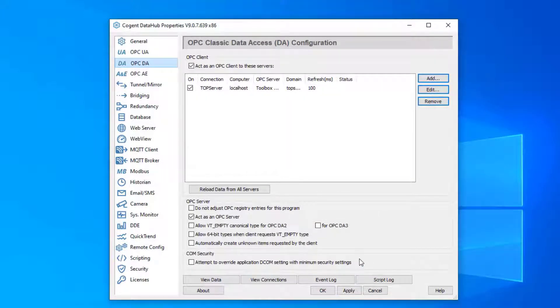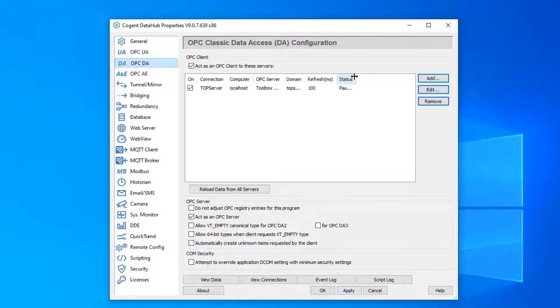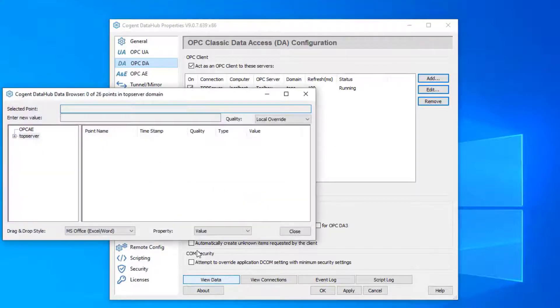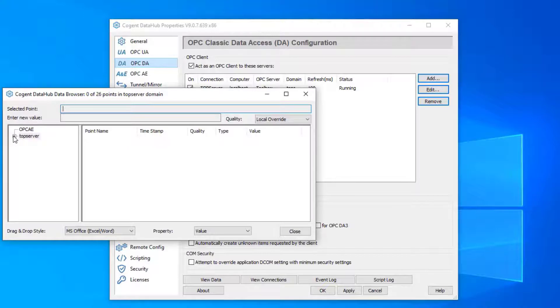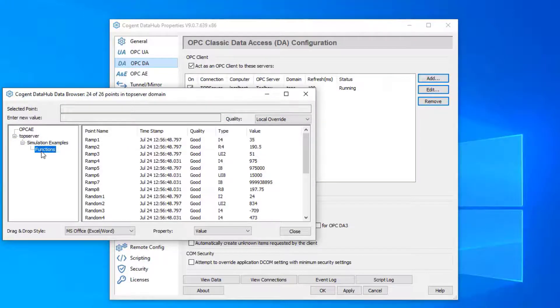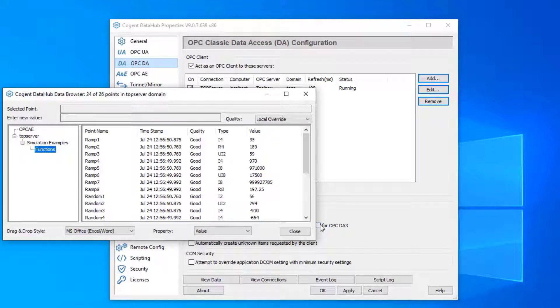One of the things that you always have to do in the data hub is click the apply button. The apply button saves the configuration and activates it. If we click OK or apply, we saw our status went to running rather quickly. That's what we want to see. Running means we do have a connection to the server, and if we go to our view data and browse, we see we have good quality data that's changing rapidly. So we've done the OPC DA to data hub part of this connection.